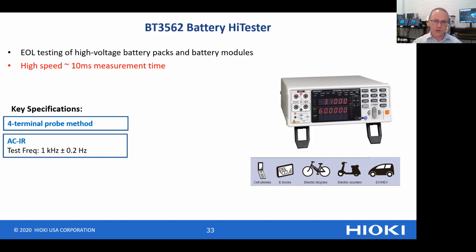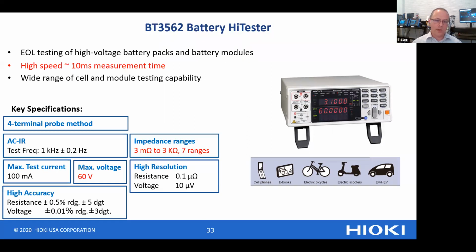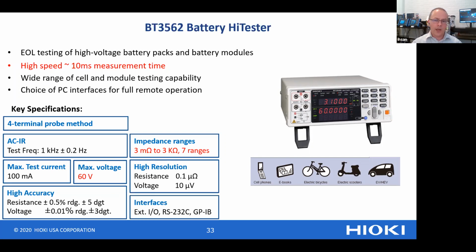One solution that Hioki has is the BT3562 battery tester. It has a single fixed test frequency of 1 kilohertz, and it uses the 4-terminal probe method, as mentioned before. Its maximum open voltage level is 60 volts. So it's able to measure not just individual cells, but also modules or multiple cells connected together, and has a very wide impedance range of 3 milliohms to 3 kilohms. It also has a range of interfaces for production testing, for instance, RS-232 and GPIB.